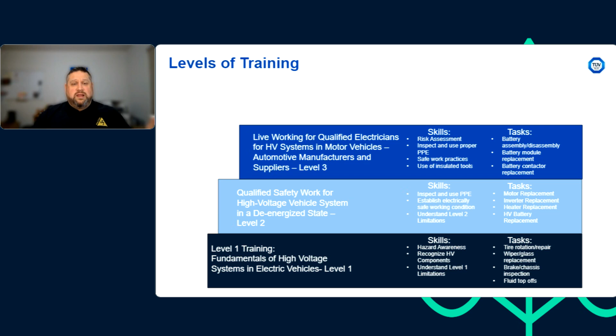So level 3 interfaces with high voltage components, including, potentially, servicing individual batteries. Some manufacturers are designing with that in mind currently, where they might go into a service center, open up the battery itself, and replace individual modules. If that's being done, those workers absolutely need level 3 type training. So those are the 3 levels we typically see as industry practice currently.